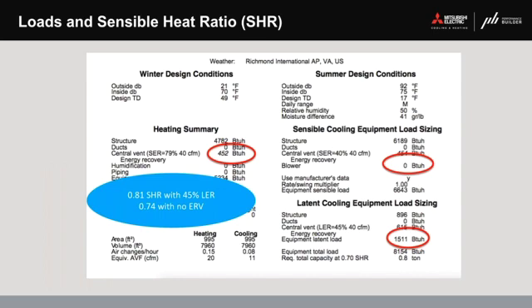Now we're going to talk a little about what's called a sensible heat ratio. This is really important because the load profile, the energy usage of our buildings, has been changing fairly drastically over the last 5 code cycles. As a result of paying close attention to the requirements of our building envelopes—insulation, infiltration, glass specifications—our sensible loads, our heat loads, have drastically decreased.